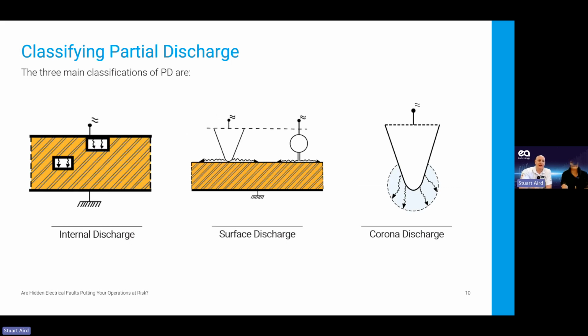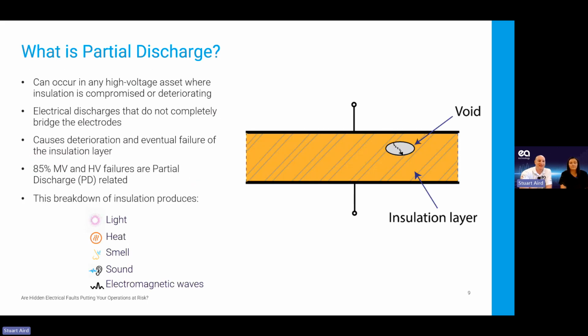So what is PD? Each type of PD will have a breakdown of the insulation, and it will cause different processes. So every type of partial discharge will give an emission. So we can get these emissions. We've got light, we've got heat. So light will be a little arc inside that insulating material. We've got heat, so it starts to break down and it's got some heat there, but it's not enough that a thermal camera will pick it up.